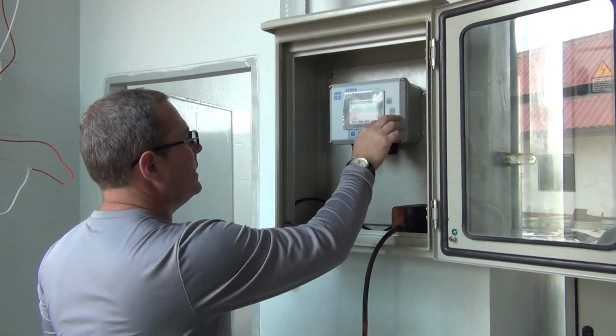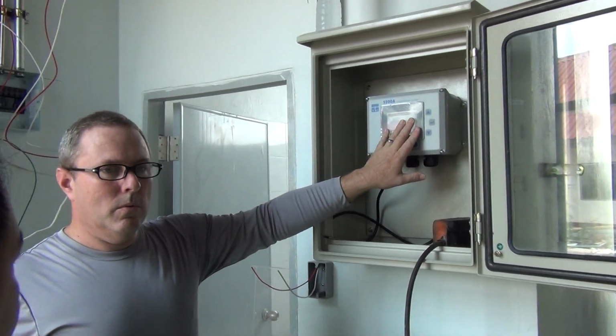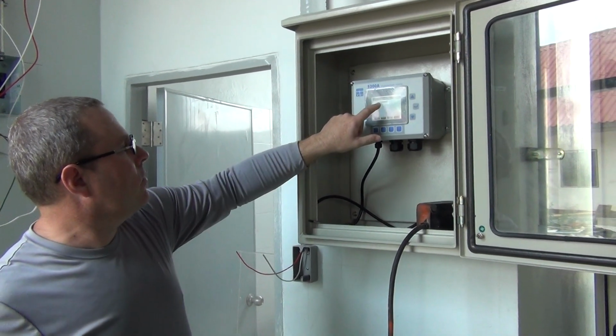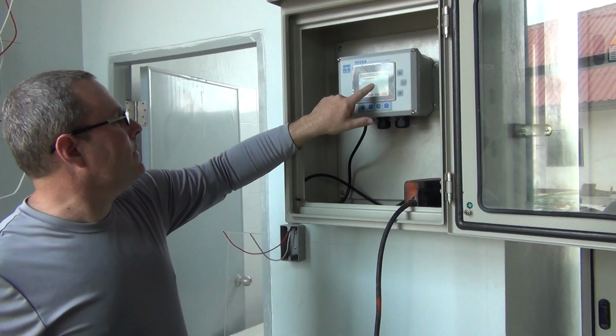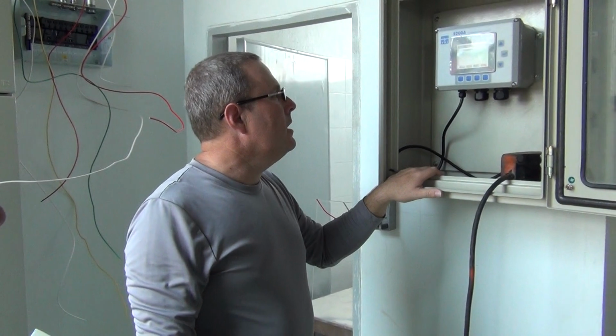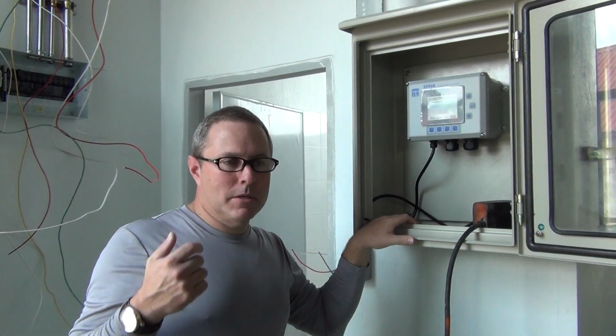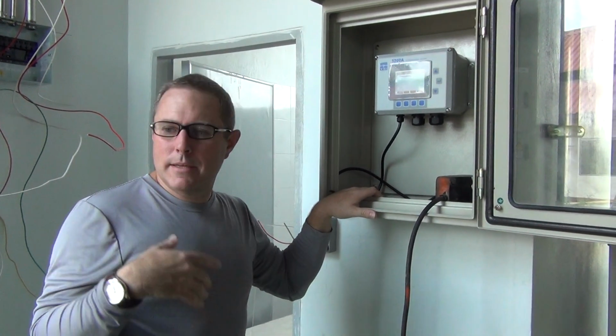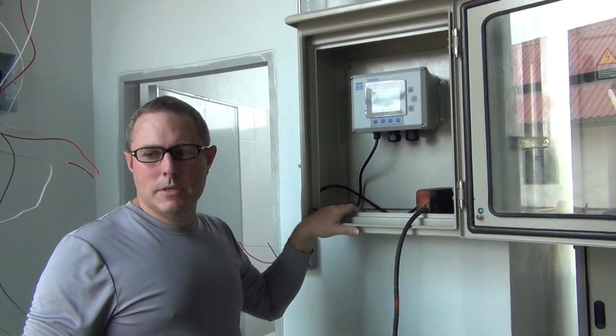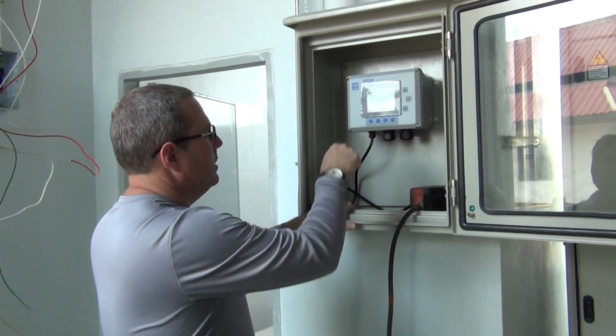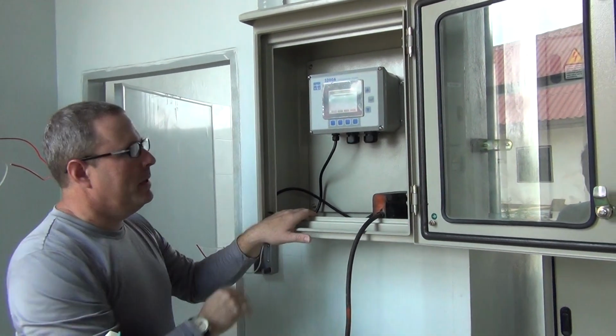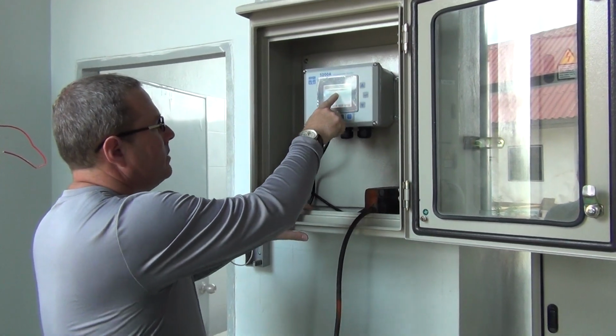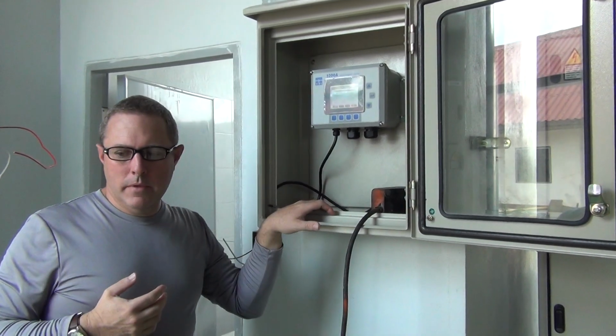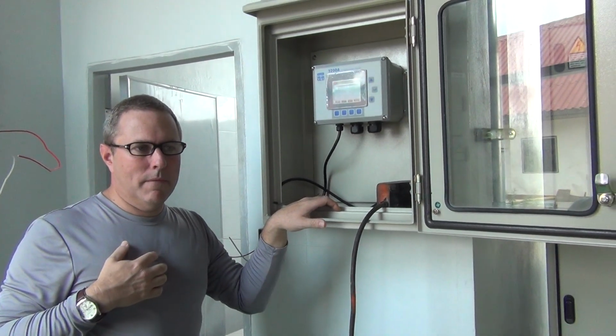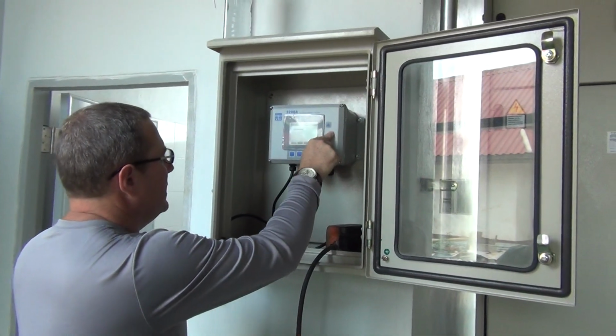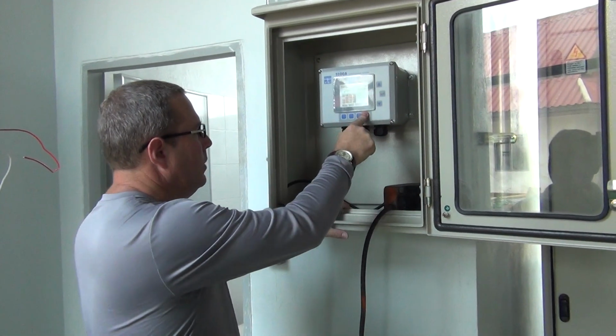So then, service. Service is a mode that we can go into when there are problems. So we go into service: reset clean probes timer, reset to factory, and output test. This is where the probe is supposed to be cleaned on a preset schedule to make sure that it doesn't foul. Every time the probe is cleaned, you would go into the service mode and push enter. First you would set how many days between probe cleaning, and then how many days duration between each one.